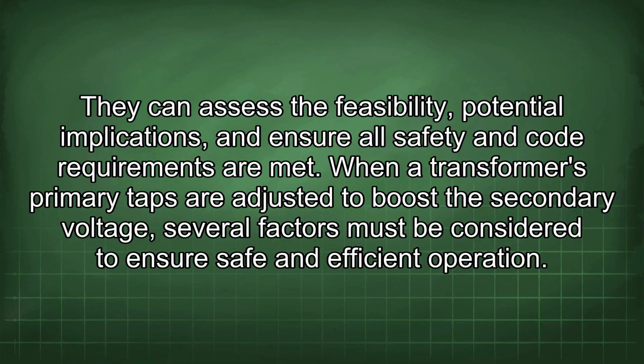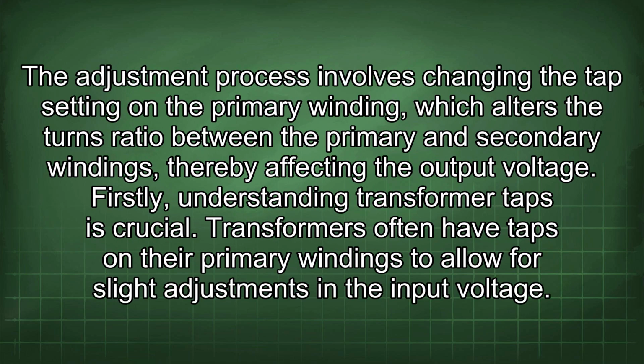When a transformer's primary taps are adjusted to boost the secondary voltage, several factors must be considered to ensure safe and efficient operation. The adjustment process involves changing the tap setting on the primary winding, which alters the turns ratio between the primary and secondary windings, thereby affecting the output voltage.